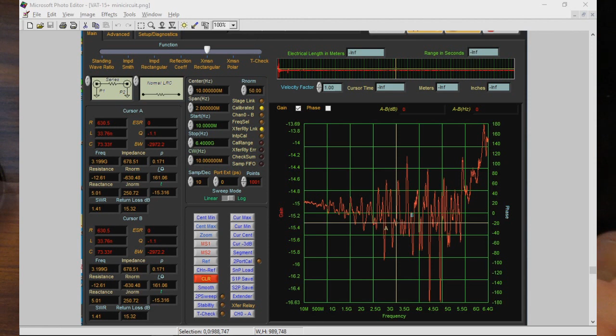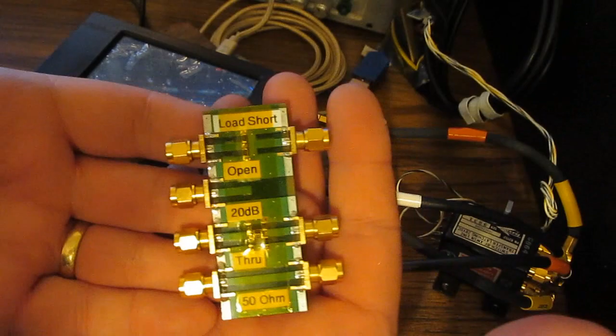I want to be clear that calibration is not a panacea. This is looking at section 1.3.2. Engineers inexperienced with the use of the VNA commonly try to use low-cost, low-quality cables with the expectation that the VNA will remove any performance issues related to these interconnects. The fallacy with this lies in that poor quality cables and interconnections rarely show systematic performance. So for this first experiment, we'll be using our homemade standards to calibrate the VNA.